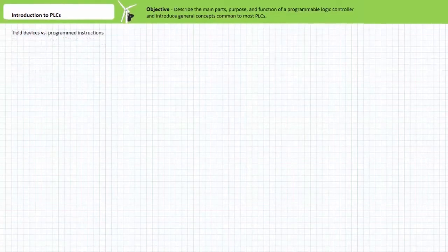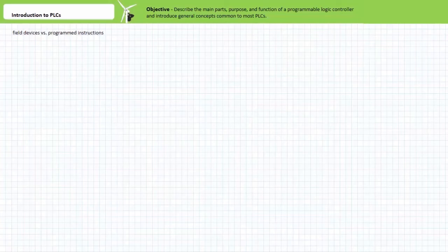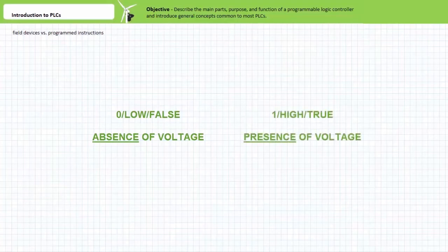An important concept central to all PLCs is the difference between field input and output devices and programmed instructions. A field device is that physical switch or coil that really exists and really interfaces with the real world. A programmed instruction in contrast is the symbolic representation and result in manipulation of input and output status used by the PLC program to make decisions. The values manipulated by a PLC are logical states symbolized by 0, low or false being the absence of voltage and a 1, high or true being the presence of voltage.